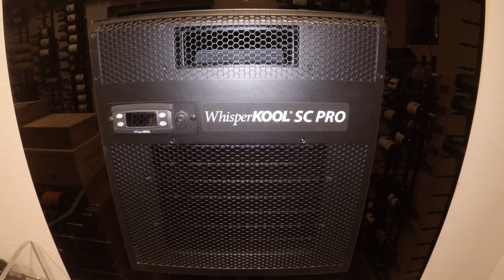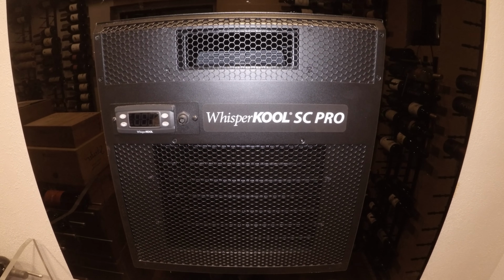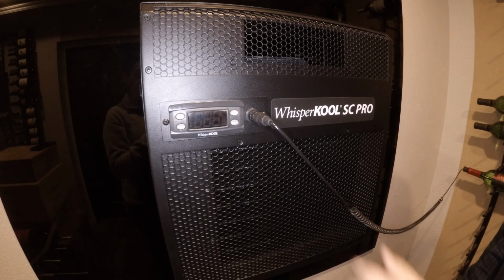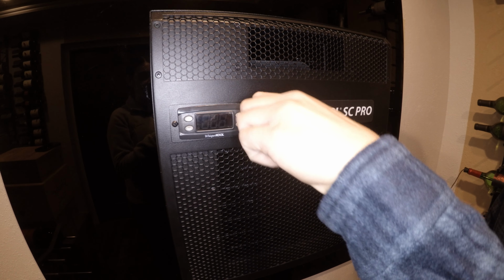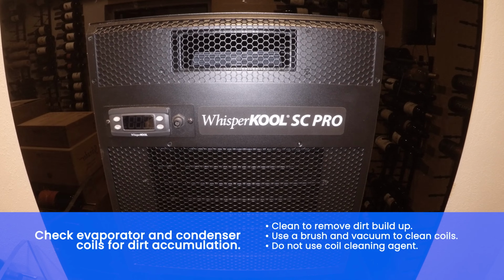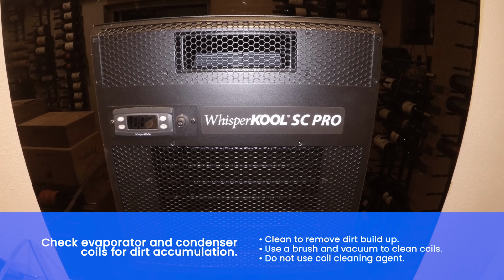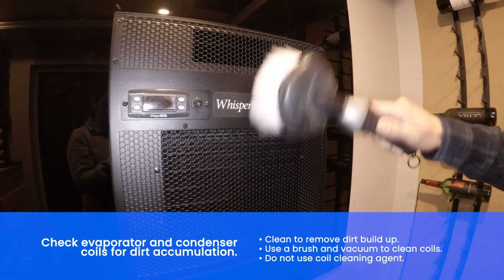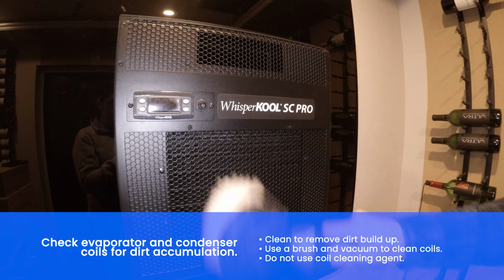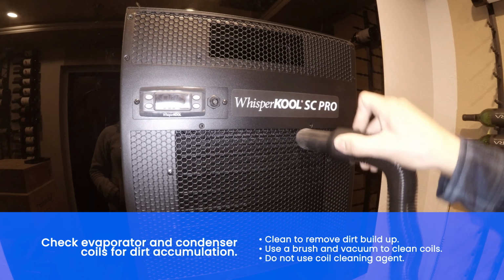In this video, we'll be reviewing the maintenance steps for the SC Pro series. Disconnect the bottle probe from the system. Check coil for dirt accumulation. Clean to remove dirt buildup. Use a brush and vacuum to clean the coil.